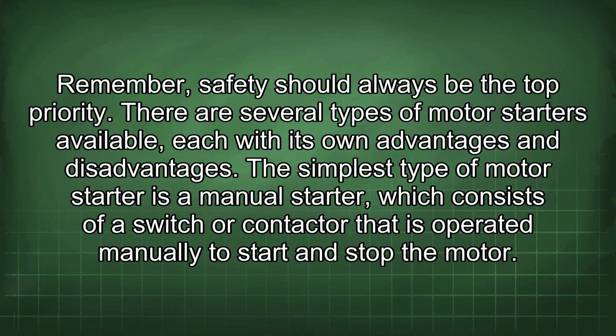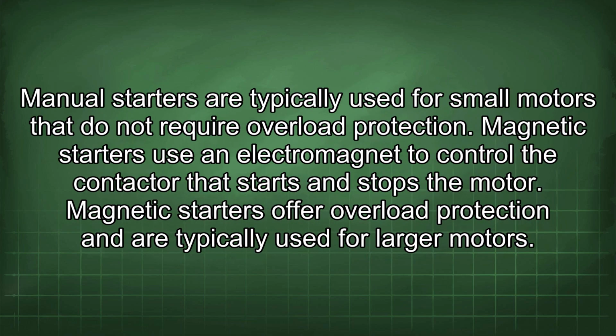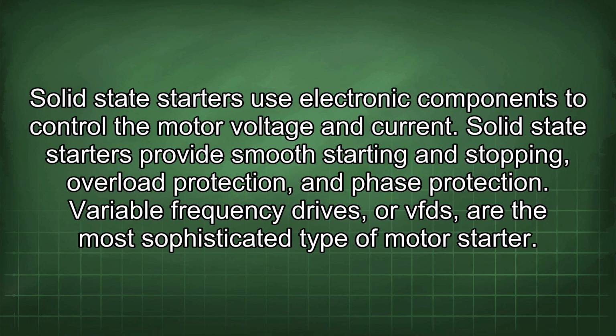There are several types of motor starters available, each with its own advantages and disadvantages. The simplest type of motor starter is a manual starter, which consists of a switch or contactor that is operated manually to start and stop the motor. Manual starters are typically used for small motors that do not require overload protection. Magnetic starters use an electromagnet to control the contactor that starts and stops the motor. Magnetic starters offer overload protection and are typically used for larger motors. Solid-state starters use electronic components to control the motor voltage and current.